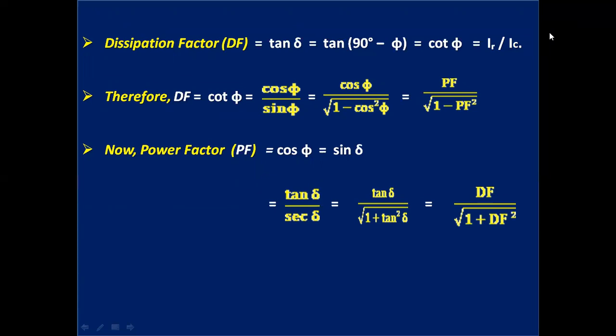Now, power factor PF is equal to cos phi, that is equal to sin delta, that is tan delta by sec delta, equals tan delta divided by root of 1 plus tan square delta. Therefore, power factor PF equals dissipation factor divided by root of 1 plus dissipation factor square.